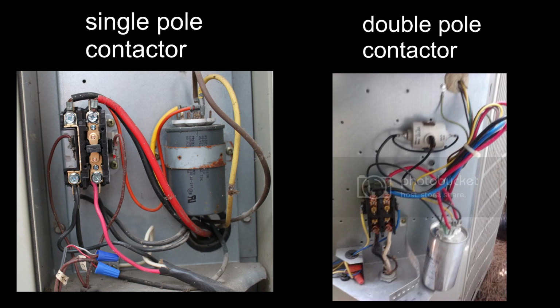The condenser fan motor has one that goes over to the capacitor, and it says fan. The other two go in there that feed over to the far side, and it gets power from it. Now, depending on fan motors, and we'll get into that, they're either 3-wire, which is usually factory, or 4-wire, which is universal. But let's go over the contactor itself.